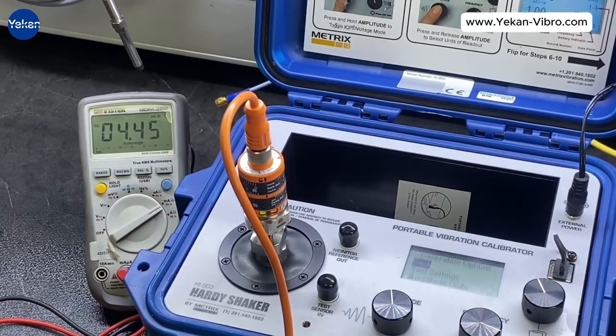According to standard ISO 16063 Part 21, this calibration was performed in a back-to-back setup. There are two types of tests: frequency test, sensitivity stays fixed, frequency is changed from 10 to 1000 Hz and error is recorded. Sensitivity test, frequency is fixed at 100 Hz and amplitude is changed from 1 to 25 millimeters per second, then error is measured and compared with a reference sensor.